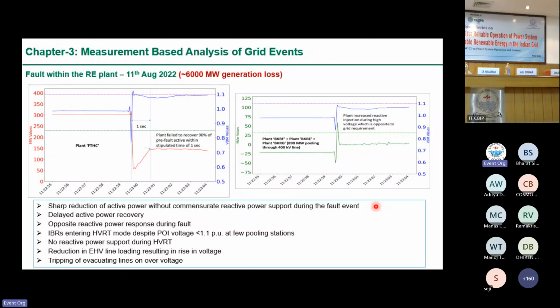Also, some of the plants which provided satisfactory response, the response came after the clearance of the fault or after the voltage had recovered. All this resulted in high voltage after the clearance of fault. Another reason for this high voltage was the delayed active power recovery. RE plants, as they have to provide reactive power support during the voltage dip, can reduce the active power if the rated current limit gets exceeded. But in this case, there was almost minimal or opposite reactive power support from most of the plants. At the same time, there was a reduction in active power also. And then there was this delayed recovery of active power.